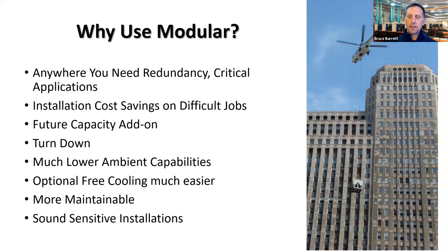Optional free cooling is much easier with a modular chiller. We've got a couple of different variants that I'll talk about. More maintainable, and by that, I mean when you've got modular chillers in an array, if you do have a failure of a component, hopefully you've built in some redundancy there and it doesn't become an emergency. You can maintain your chilled water capabilities even with a failure of a singular component.